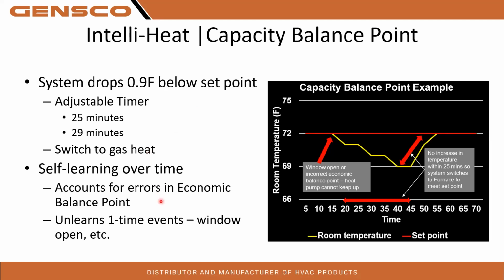This is self-learned over time and will change itself, but it also unlearns one-time events. So if there's a window open, doors are open, kids are running in and out of the house, whatever it may be, if it has that changeover, it's going to revert itself back. So it's going to take time for it to relearn itself to make sure everything's okay, but it will do it. What will end up happening is once it sees that one-time event, the next time it goes through its startup, it's going to slowly work the temperature down. And if it doesn't see a temperature change within 25 minutes, it's going to revert back to its learned balance point. But if it sees that it is gaining temperature on its own with just the heat pump, it'll continue to run the heat pump and adjust itself.